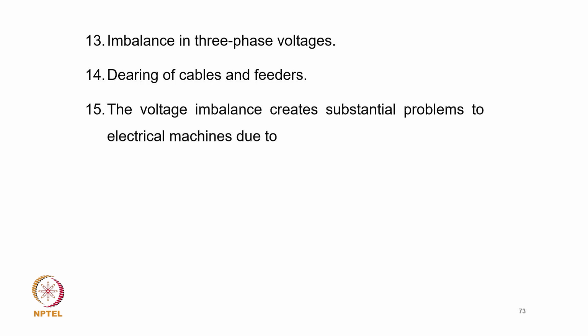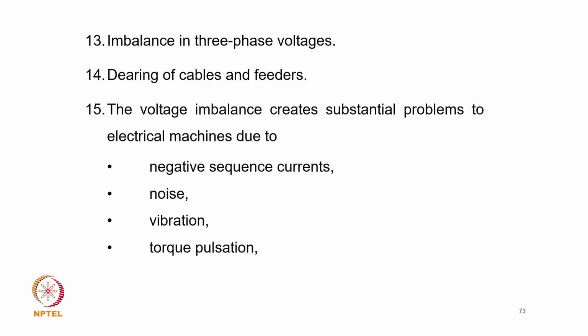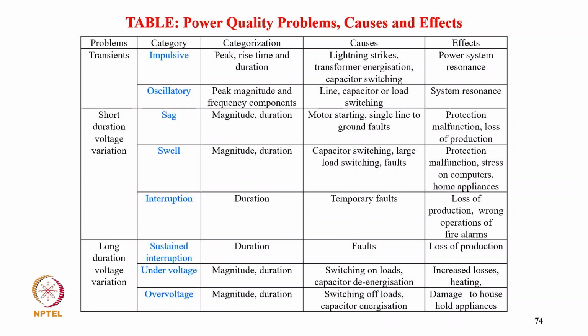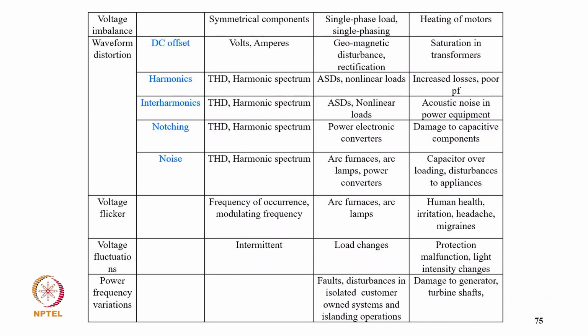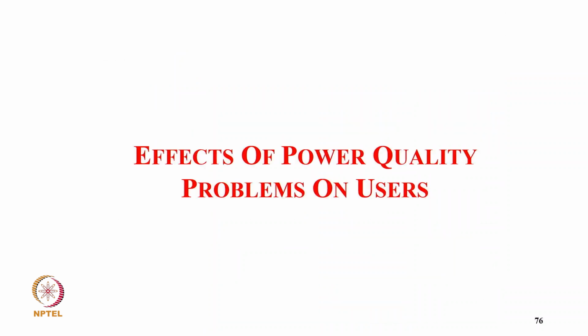The voltage imbalance creates substantial problems for electrical machines due to negative sequence current, noise, vibration, torque pulsation, and rotor heating. Of course, there is also derating. This is a table of power quality problem causes by type: short duration voltage, long duration voltage, with categorization of causes and effects, and voltage distortion, voltage fluctuation, voltage flicker, and power frequency variation.